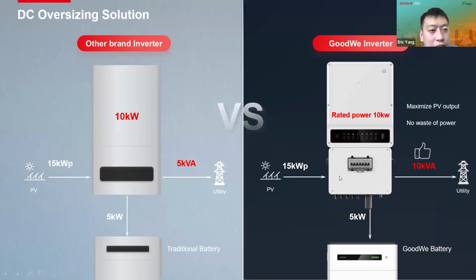And this is a DC oversizing solution. For example, if the inverter is 10 kilowatts, for GoodWe we suggest the customer connect 15 kilowatts of PV panels because the maximum AC output of the hybrid inverter is 10 kilowatts, and the other 5 kilowatts of PV power can charge the battery. And the maximum is only to charge the battery with 5 kilowatts.